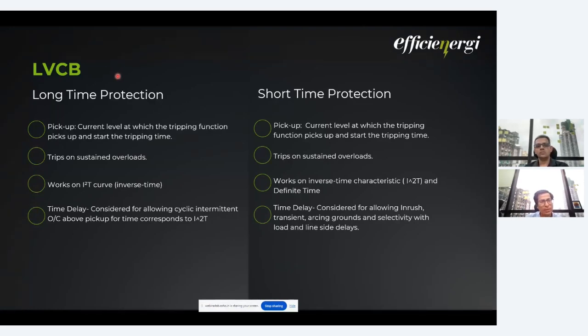Normally we use air circuit breakers here. For LVCB, the familiar term is always LSIGN: long time, short time, instantaneous, ground fault, and neutral protection. Here you must have heard of long time pickup, then long time delay. Long time pickup we call IR, and time delay we call TR. In short time, we call it ISD, and for time delay, we say TSD. So again, it is a regular concept. It trips on sustained overloads and works on I squared T. Here, I will elaborate more.